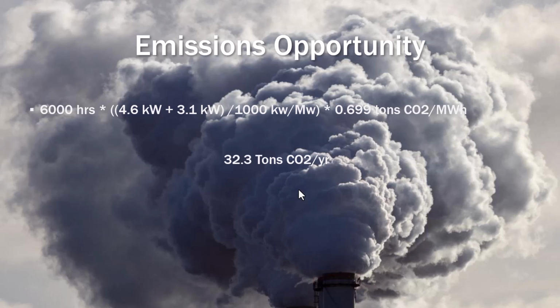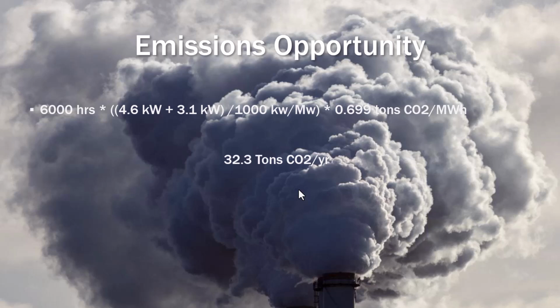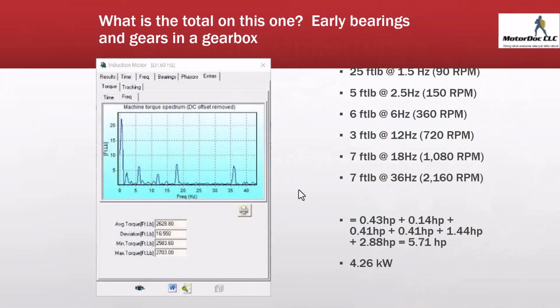And because it's so much higher and we're actually losing kilowatts, meaning it's a badly worn out belt and it's slipping heavily in the sheaves, so belts and sheaves, well, I can cost justify that with this. And then by bringing it back in and doing a precision belt alignment and proper belt tension, I can reduce 32.3 tons of CO2.